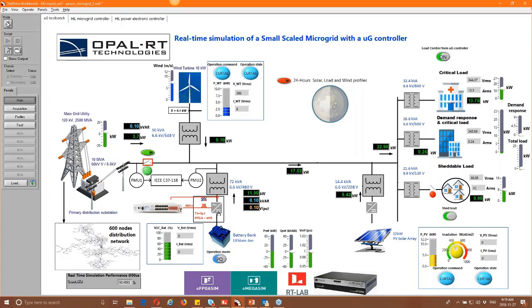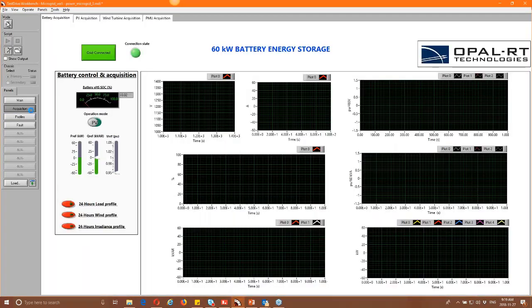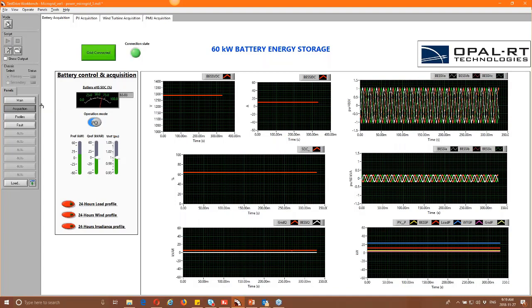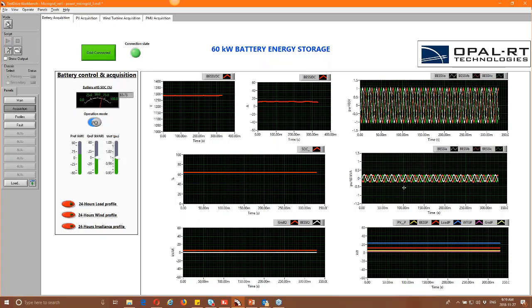Another aspect of this demo is that the power electronics of the battery energy storage system are simulated on an FPGA running at a 1-microsecond time step, while the whole network runs at a 50-microsecond time step. This allows us to see the current ripples on the battery energy storage system, whereas the other DERs — implemented as average model converters — show clean waveforms. The BESS current clearly displays the switching ripple inherent to the detailed power electronics model.